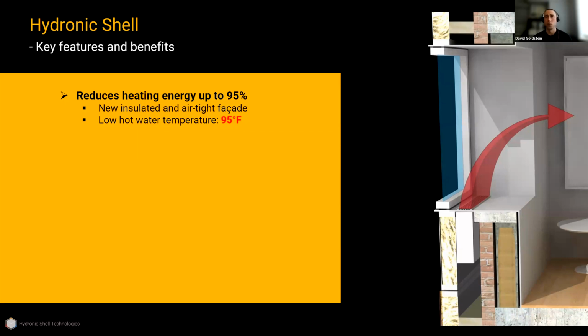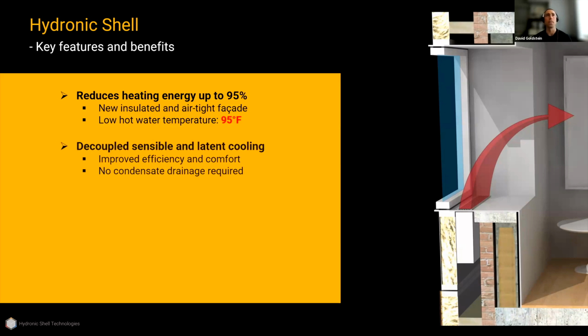So one is huge reduction in heating energy consumption, up to 95%, which sounds almost unbelievable, but it's really very possible because we're insulating the building. We're taking a building that is not insulated and making it super insulated. So that alone could be 80, 90% heating reduction. And then on top of that, we have a super efficient heat pump system that's using 95-degree hot water. So that's much lower temperature than a typical heating system, which means the heat pumps operate much more efficiently.